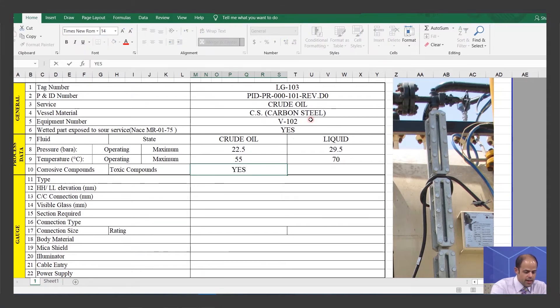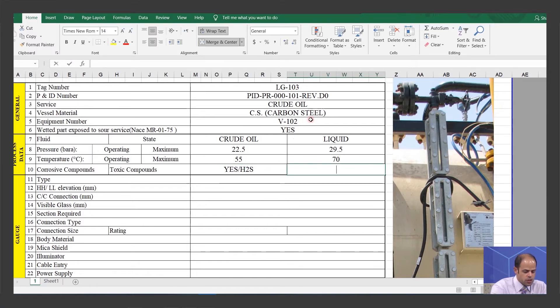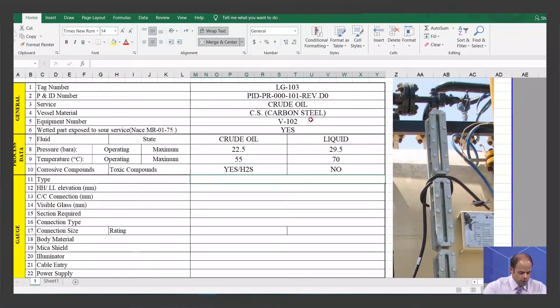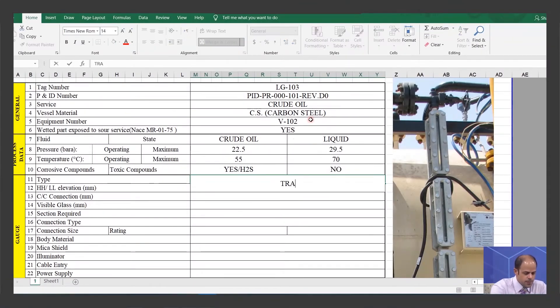Corrosive? Yes, we have. And this one is sour gas, which is H2S. Then about toxic, no, we do not have any toxic item. As you know, crude oil has a dark color. So in this situation, if you want to consider a suitable sight glass, you need to consider the transparent. As you know for transparent, you must consider the illuminator because at night you can see all the things through this one clearly. I want to tell you that at night it's totally visible. So do not forget these matters. Now I want to reflect all these designing points in this part as well. So the type of it is transparent.